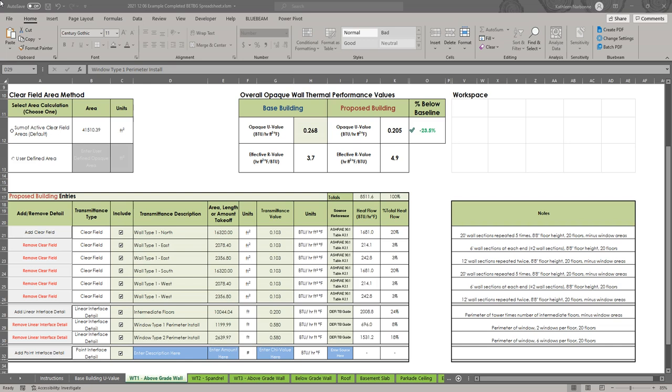I think it's more of that clear field, or as we were talking about earlier, effective R-value. I don't even think it includes any sort of thermal bridging for cladding attachment systems or insulation fasteners on the exterior side. It does account for studs, and that's probably it, because they are only really focusing on the two-dimensional heat flow through the assembly and not really the three-dimensional building interfaces. Yeah, I would agree with that. So keeping apprised of what your exterior cladding attachment system is can significantly impact the performance of your insulation. Great answer.